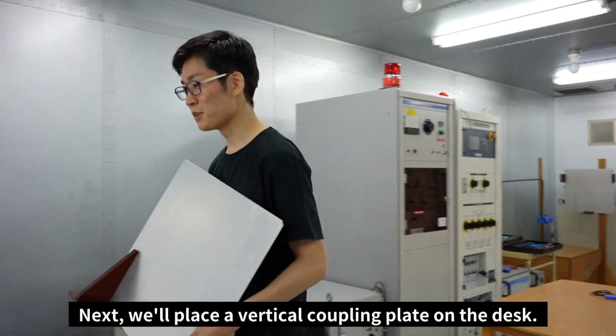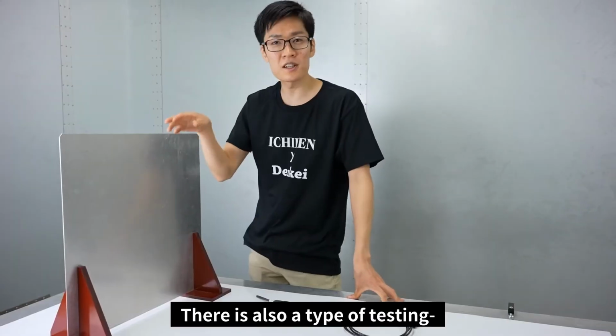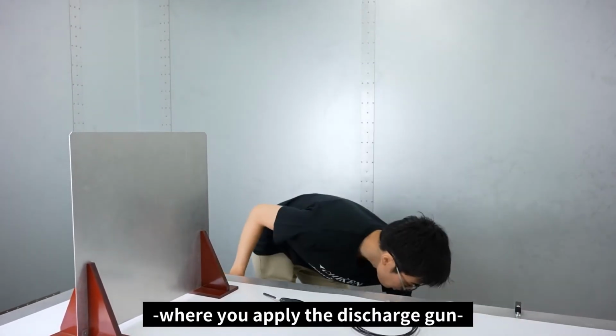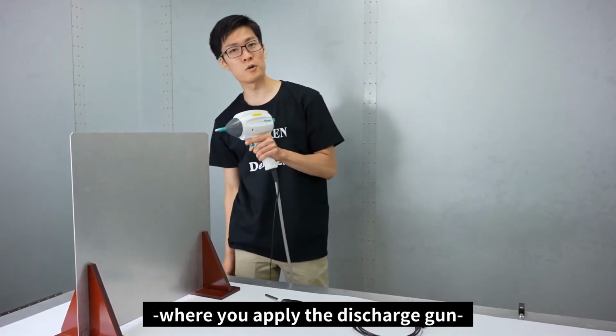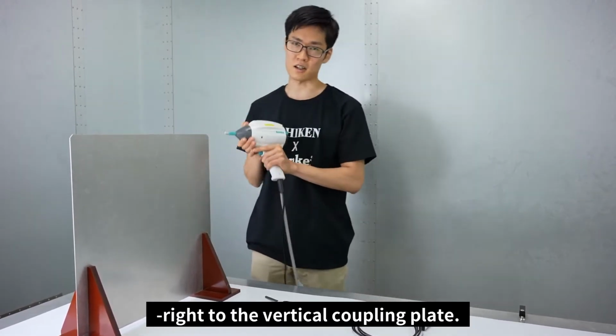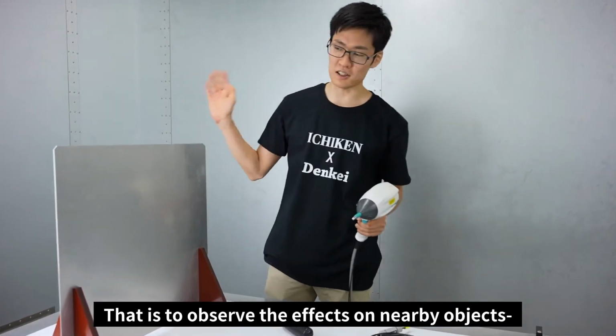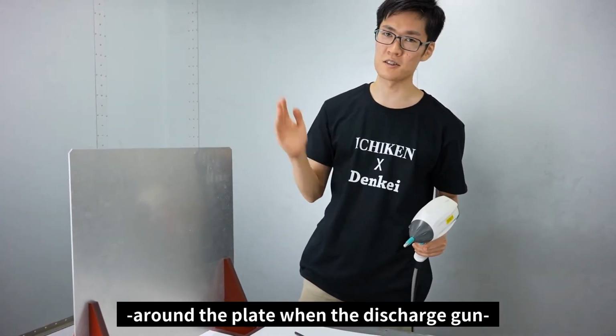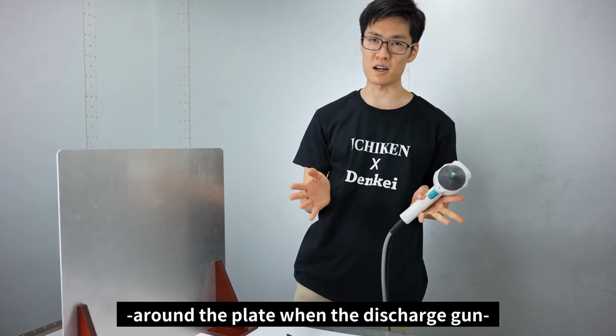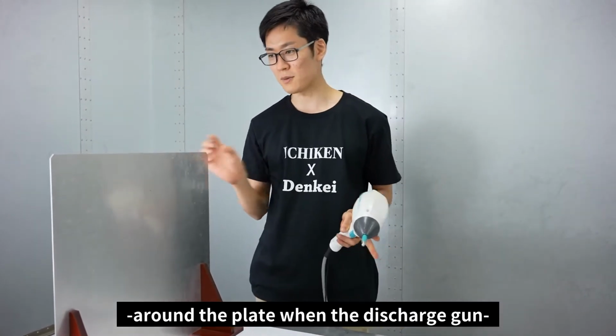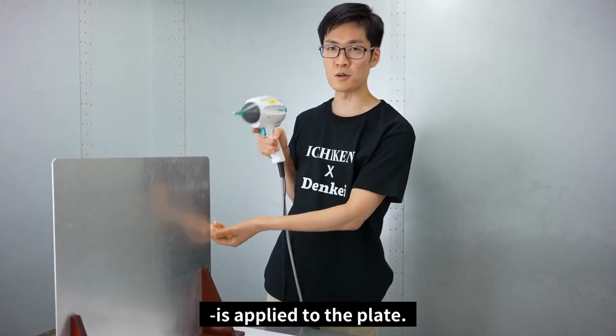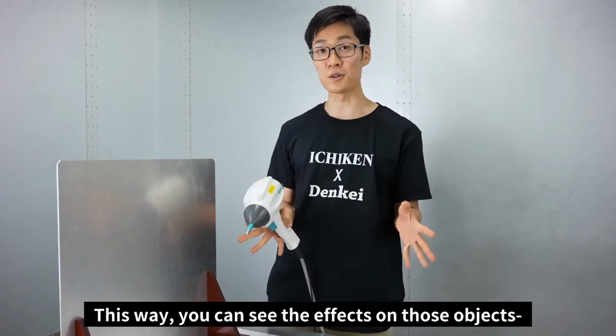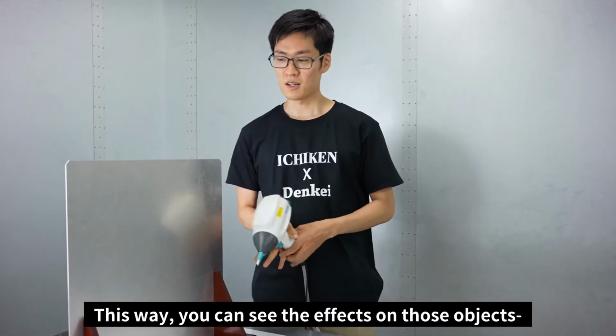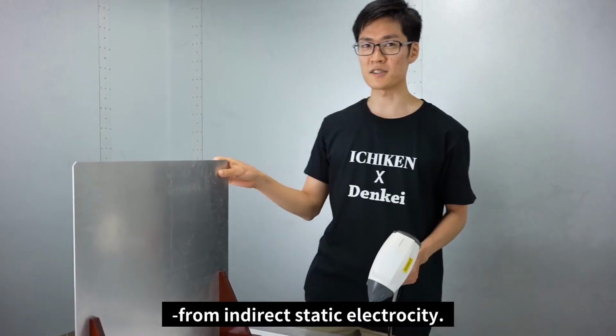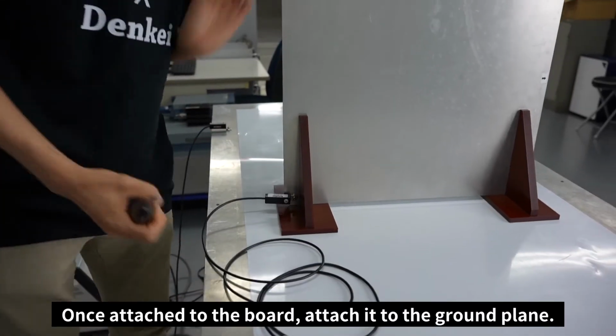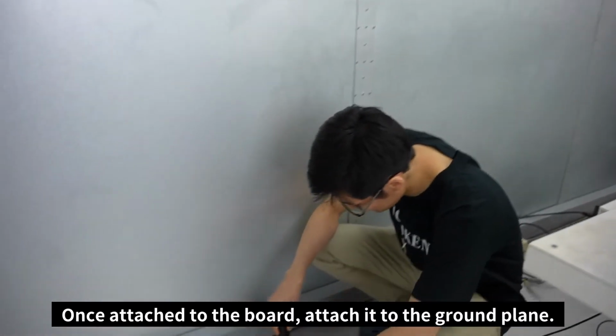Next, we'll place a vertical coupling plate on the desk. There is also a type of testing where you apply the discharge gun directly to the vertical coupling plate. That is to observe the effects on nearby objects around the plate when the discharge gun is applied to the plate. This way, you can see the effects on those objects from indirect static electricity. Once attached to the board, attach it to the ground plane.